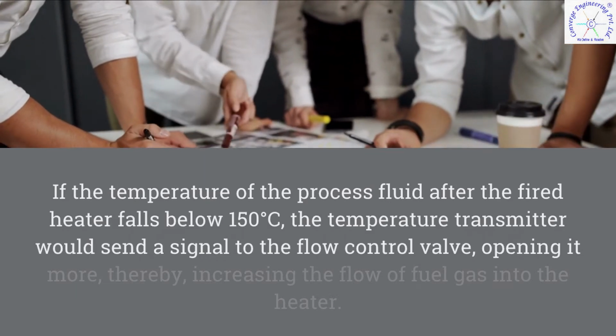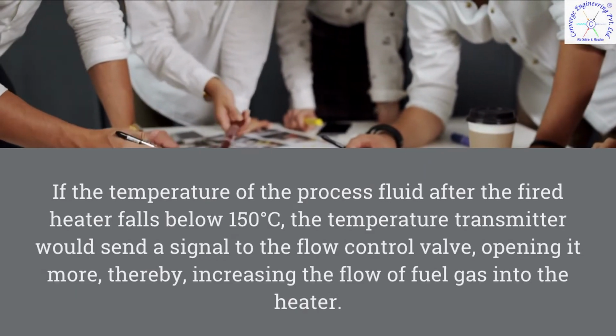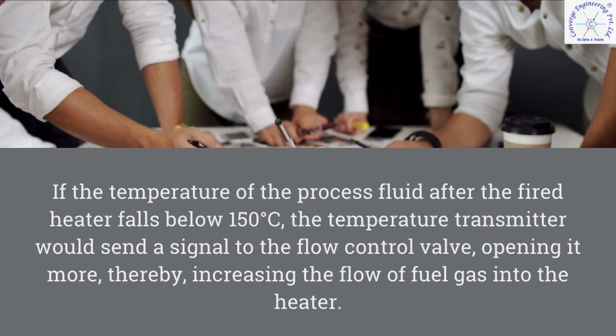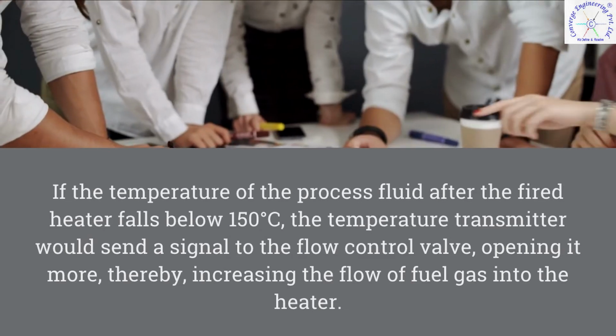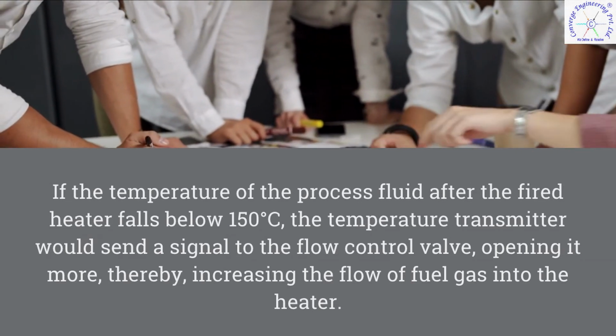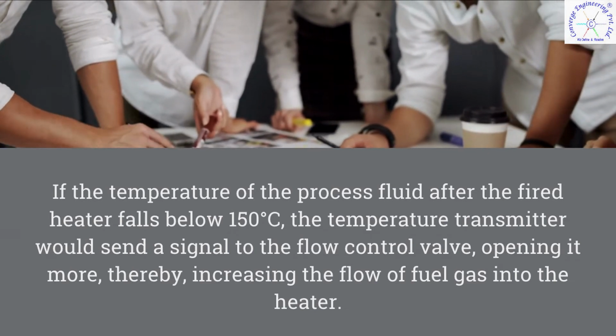If the temperature of the process fluid after the fired heater falls below 150 degrees Celsius, the temperature transmitter would send a signal to the flow control valve, opening it more, thereby increasing the flow of fuel gas into the heater.